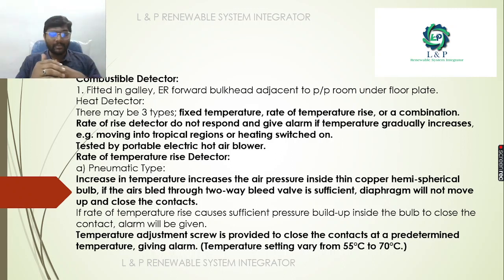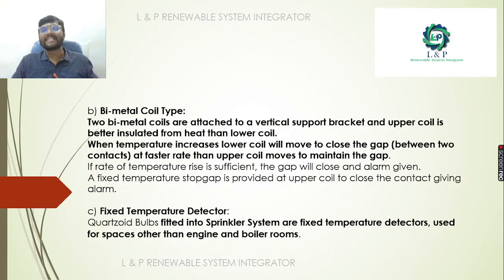There is a pneumatic type. An increase in the temperature increases the air pressure inside the copper hemispherical bulb. If the air bled through the two-way bleed valve is insufficient, the diaphragm will move up and close the contact. So we can make adjustments, and the temperature adjustment can be from 55 to 70 degrees. Next is the bimetallic coil type. It has two bimetallic coils attached to vertical support brackets, and the upper coil is better insulated from heat than the lower coil. When the temperature increases, the lower coil will move to close the contact.